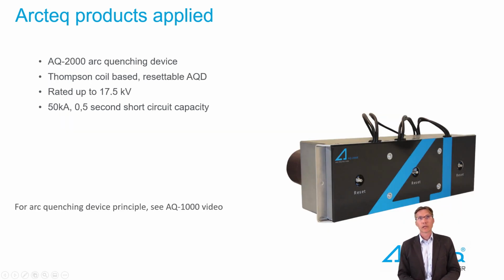And here the actual quenching device, AQ2000, for medium voltage up to 17.5 kV, based on Thomson coil. And this Thomson coil technology makes the unit resettable. Ratings up to 50 kiloamperes for half a second short circuit capacity. And so for the arc quenching device principle, we'll play here a short video describing the principle. Here we go.